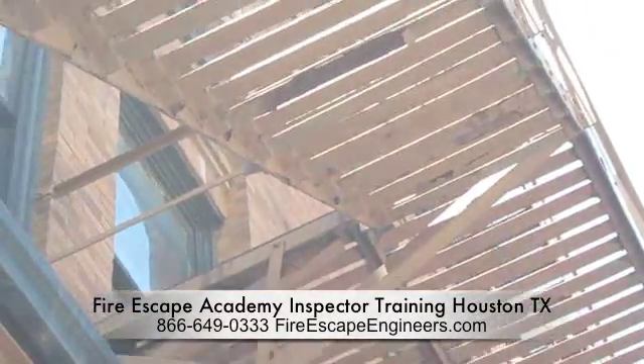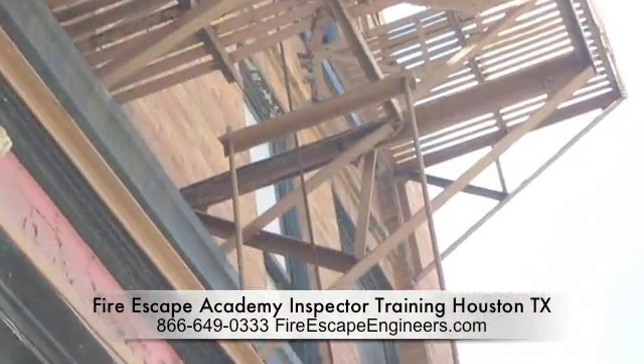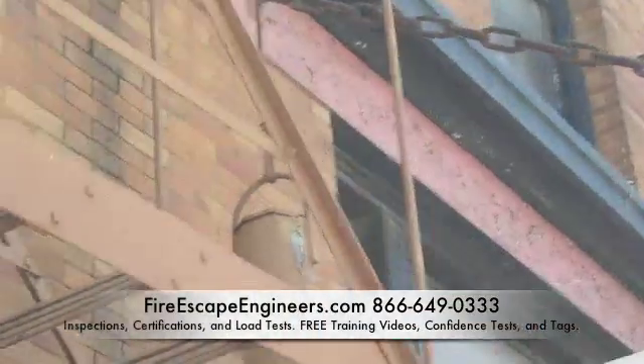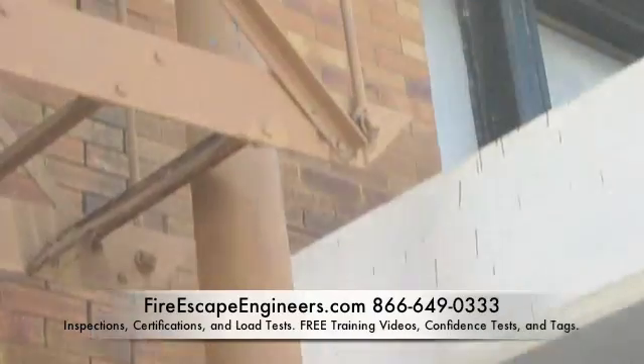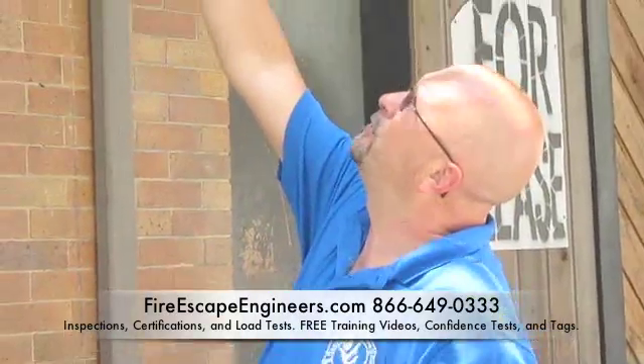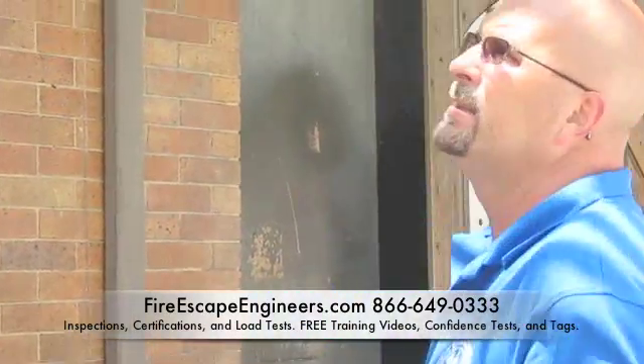There are different aspects and different points of the fire escape. This cantilever has a weight system that is above somebody's head, so if this cable was to ever let go, there's no backup catch. This needs to have something that stops it from falling and hitting somebody on the head when it comes down. It appears to foul with itself on the way up and on the way down, so that's another indicator that the fire escape is not proper.